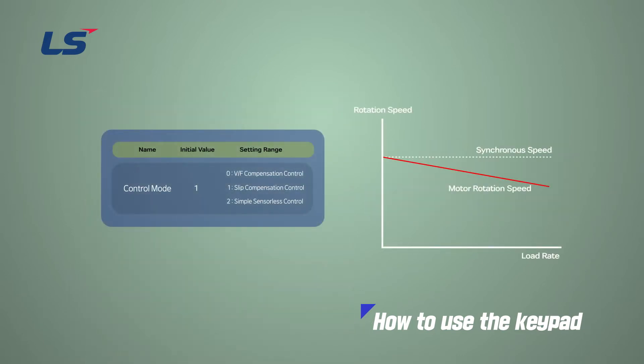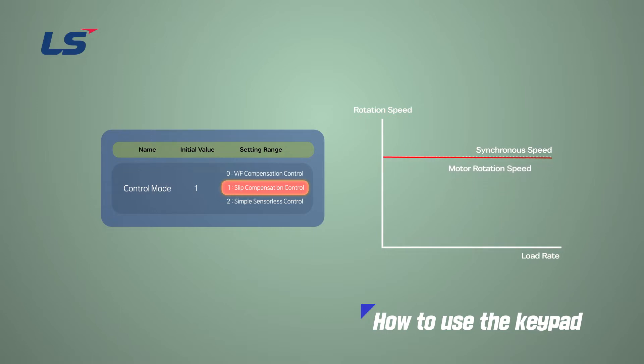In addition, M100 has the feature that the default control mode in the drive group is set to Slip Compensation Control. Slip Compensation means that the difference between the rotation speed and the set frequency of an induction motor increases according to the load factor.